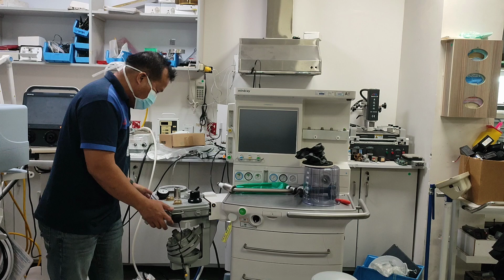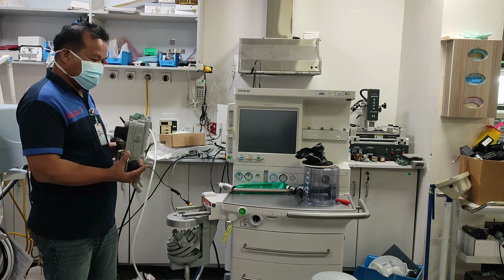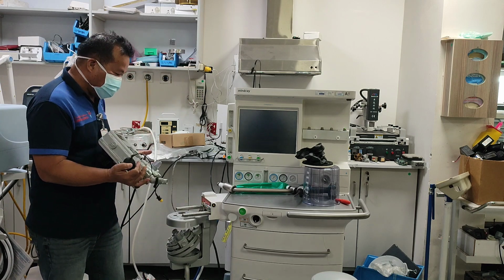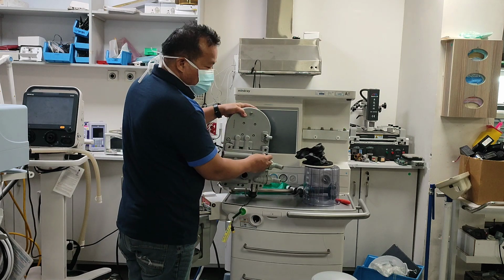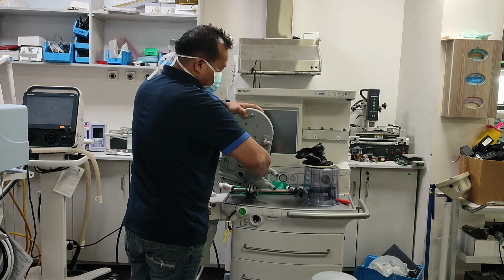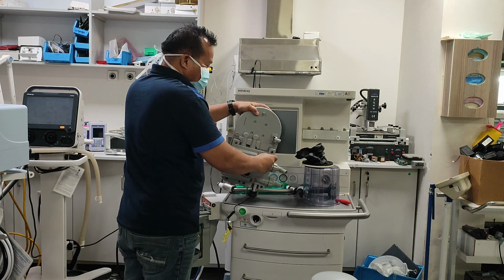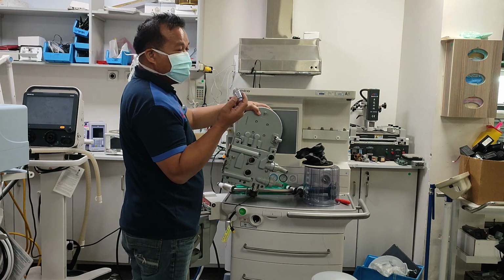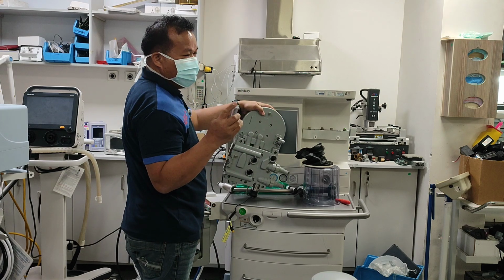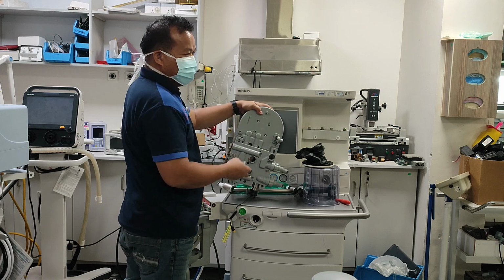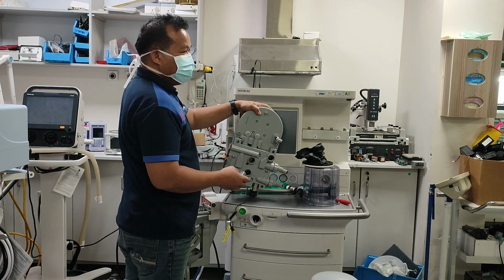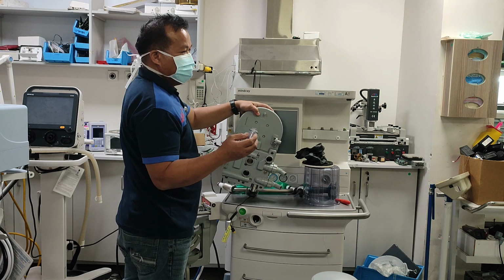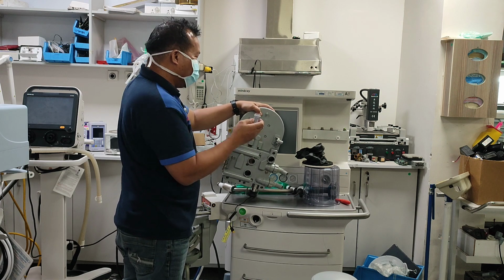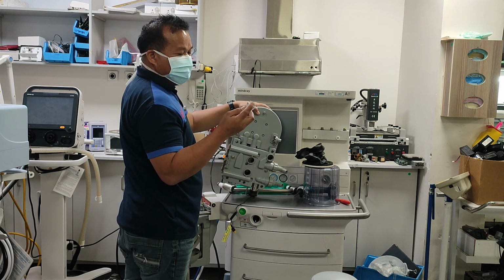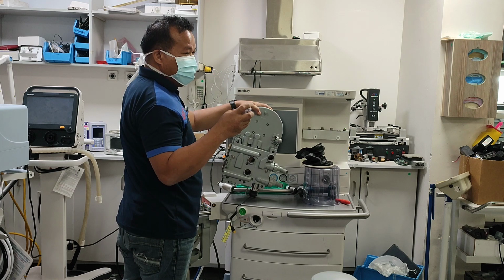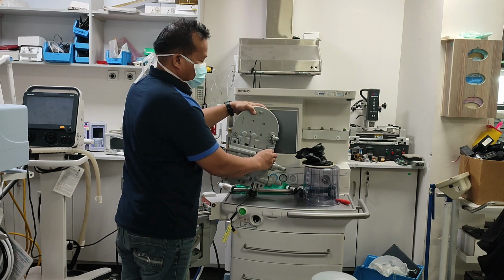So I think that's it for this one. So we have to hold also here. So the purpose for this one is very important. As a service engineer, this is very important. Once there is water here, moisture or water, it will alarm the machine. It will alarm you that the water trap is wet. So meaning water trap is wet, this is the water trap. Meaning they trap the water here. You should clean, you should remove the water and return it back on there.